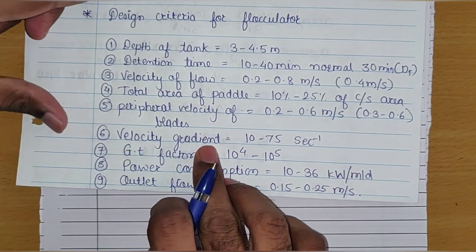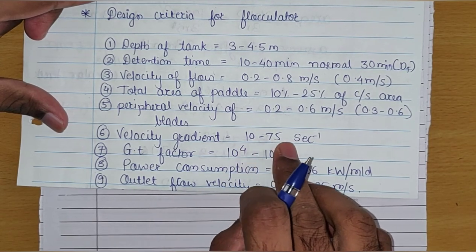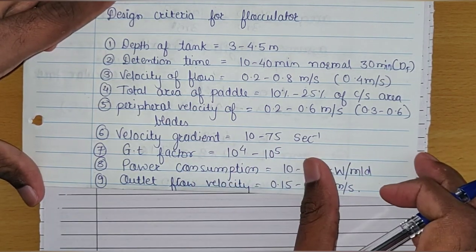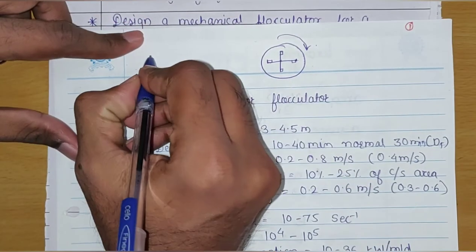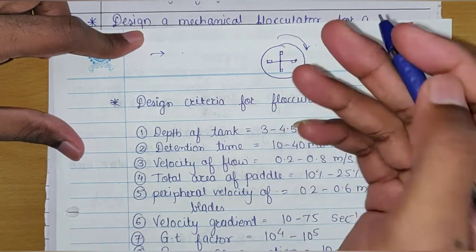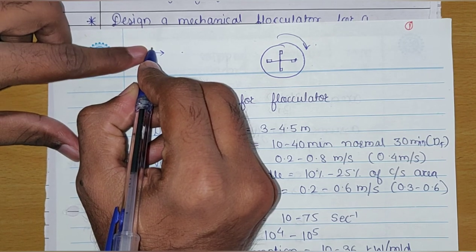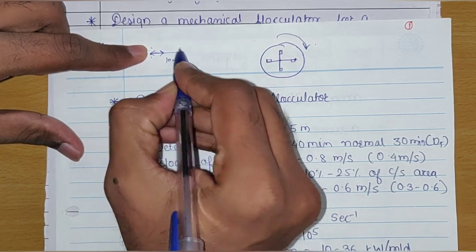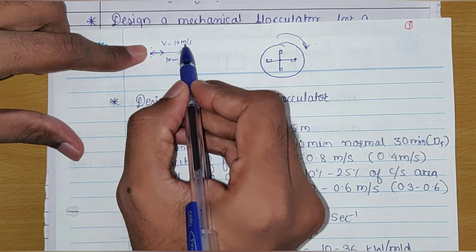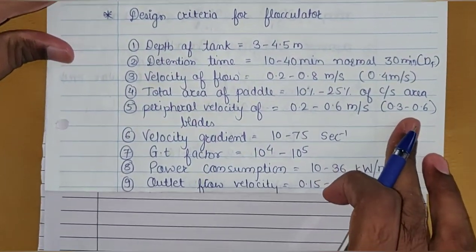The velocity gradient should be in the range of 10 to 75 per second. Velocity gradient means the rate of change of velocity with respect to distance. For example, if water is flowing from one point to another and the velocity is gradually changing, the velocity gradient is the rate of change of velocity from one point to another with respect to that distance. Suppose the distance is 10 meter and the velocity is 10 meter per second — the velocity gradient will be 10 divided by 10, that means 1 per second.